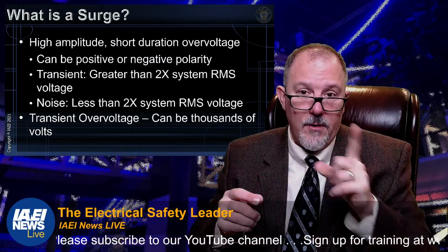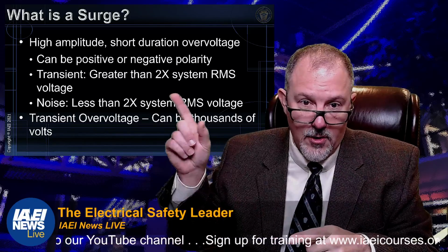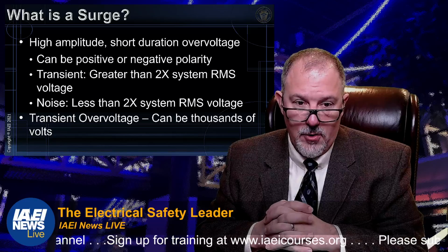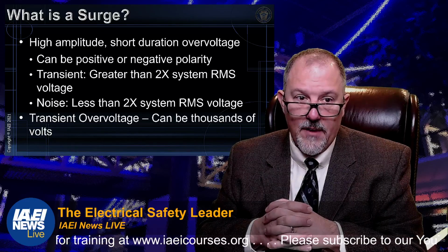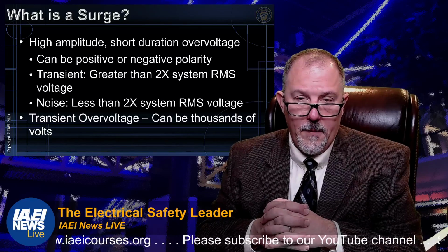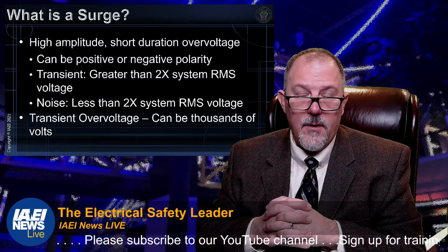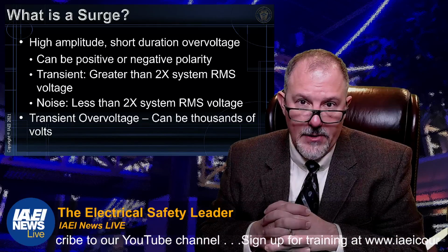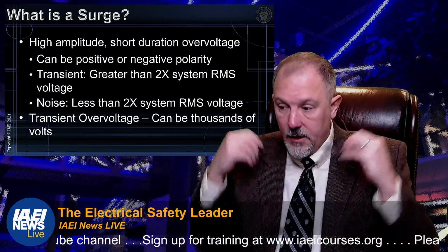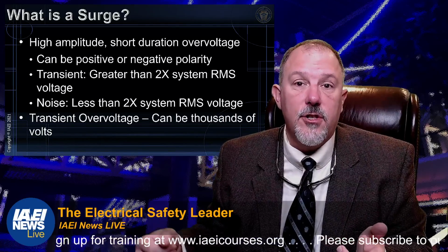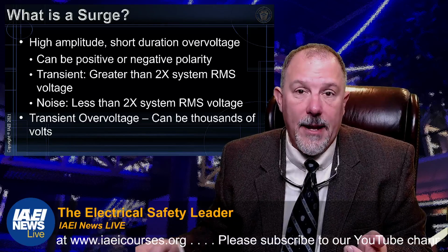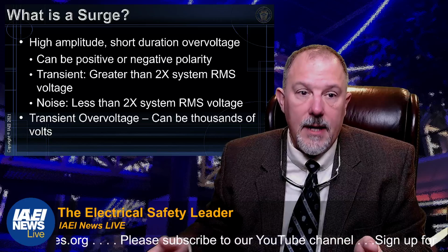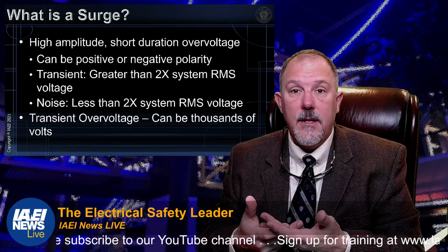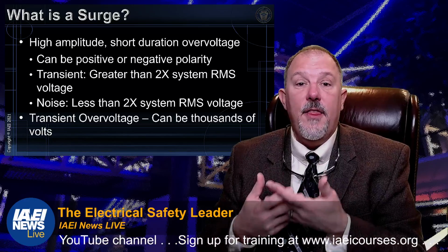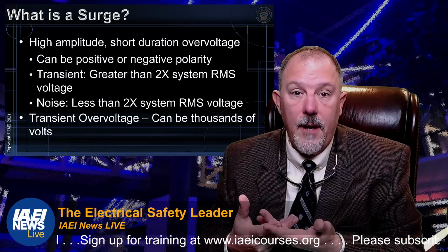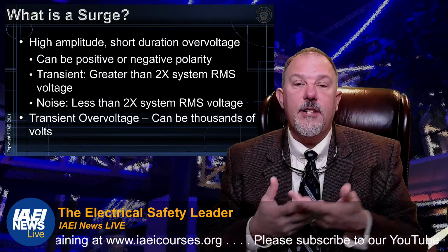There's another term you're going to see: transient. So I use the word transient there. That's another term that has been used over the years in industry to reference and talk about surge events. We're going to talk a little bit about that history as well, but that terminology transient is an important piece of the puzzle. In fact, years ago, what did we call it? We called them transient voltage surge suppression, TVSS. We've gotten away from that. Now we just call them a surge protective device. But in my opinion, that term transient is an important part of what we're talking about, because that is what helps us understand the difference between an overvoltage and a surge event.